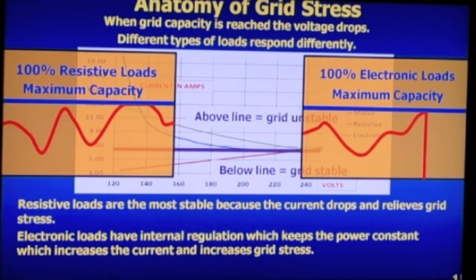But now, with electronic loads, if it ever touches that line, it guarantees the grid completely collapses, or it could be your generator on a small home. So they can't risk that. They have to run at a smaller percentage of rated load, called spinning capacity, or start peaker plants, because bumping that line will absolutely crash them. We're moving towards 80% electronic loads. Apple has a new data center with a 175 megawatt electronic load, that's a continuous draw.